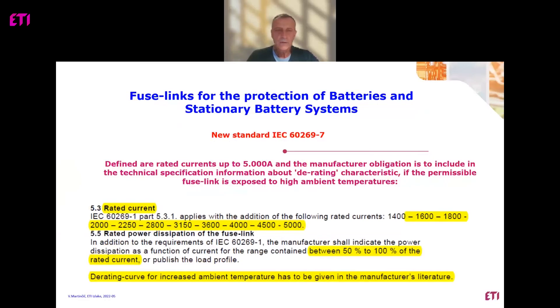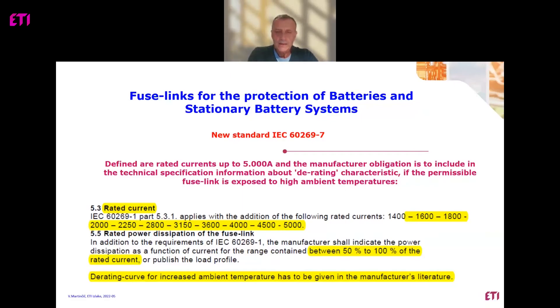Regarding rated currents: in the basic Part 1, general characteristics cover rated currents up to 1400 amps, whereas for battery systems, even higher rated currents up to 5000 amps are defined. Regarding power dissipation, the manufacturer must indicate the power dissipation at 50% and 100% of the rated current, because battery fuse links are not always loaded at 100% of rated current. As mentioned, the Derating curve for increased ambient temperature must be provided in manufacturer catalogs.